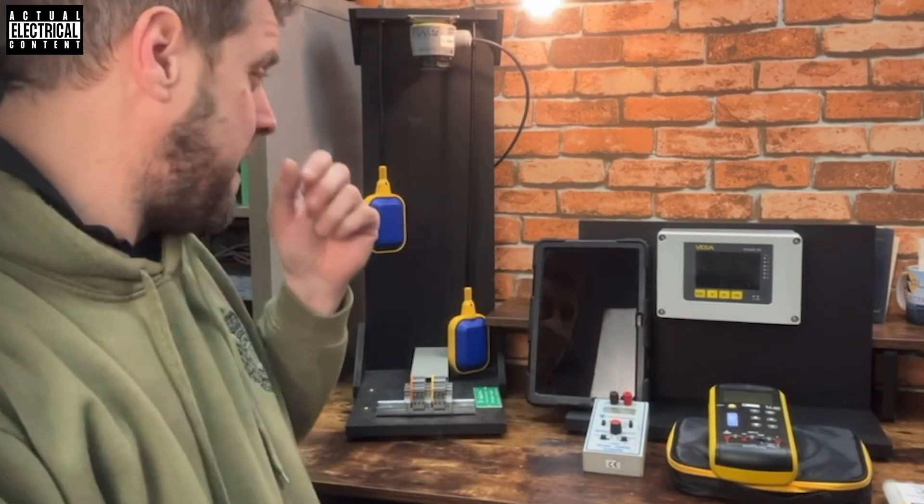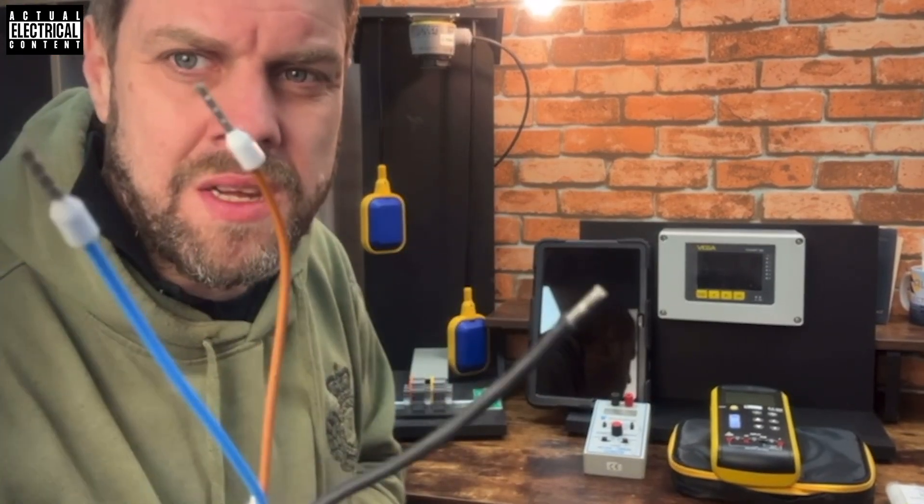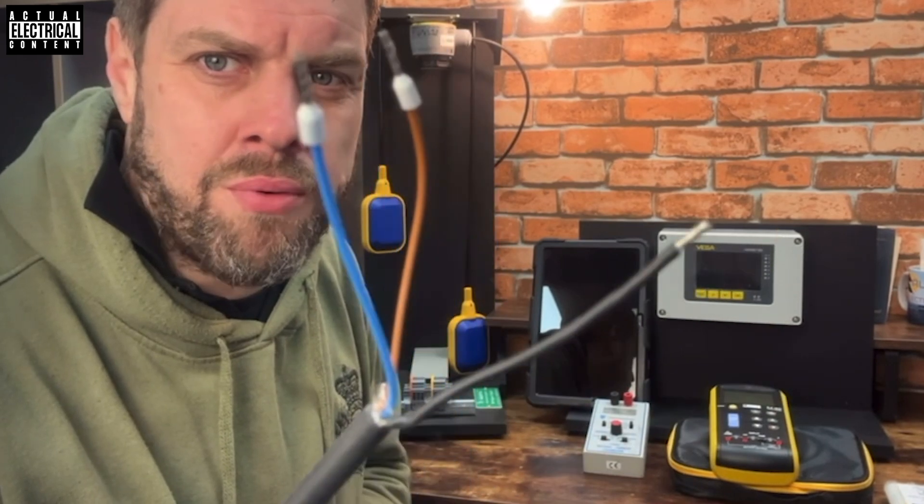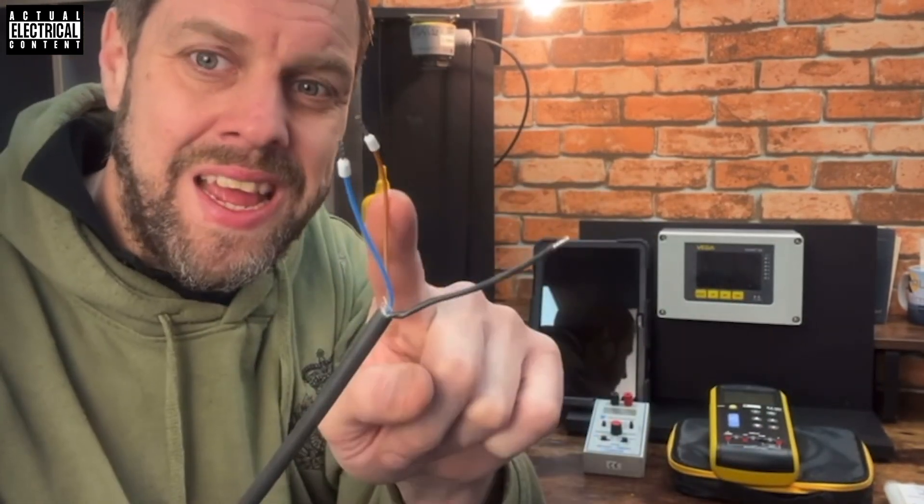Let's pretend just for now it's an instrument that I've found and we'll derive what it does from what I've got. If you look at this cable, there's two cores - a brown and a blue - and then there's this one, this is a screen. That's just a screen for the cable, so it's a two-wire instrument.